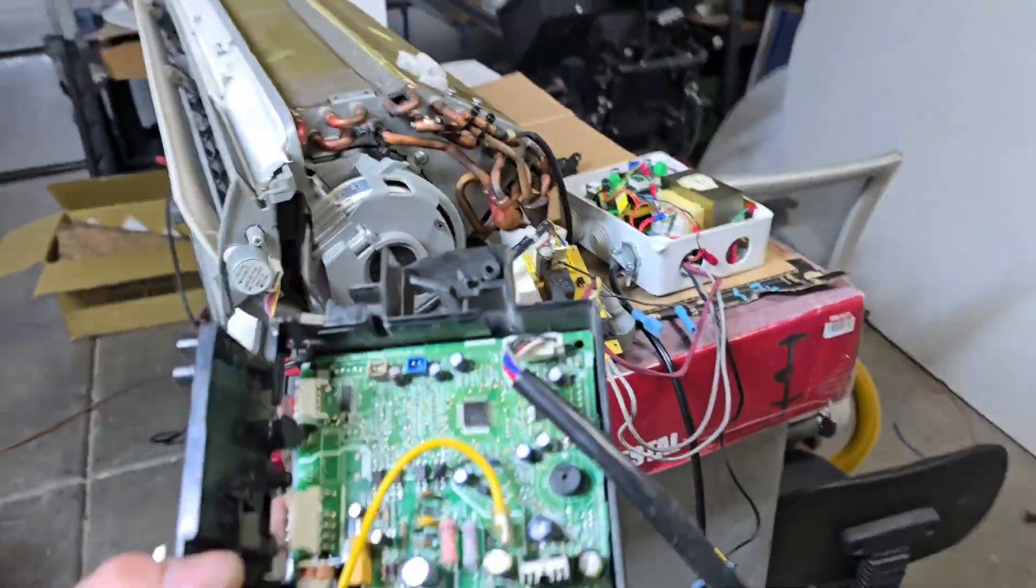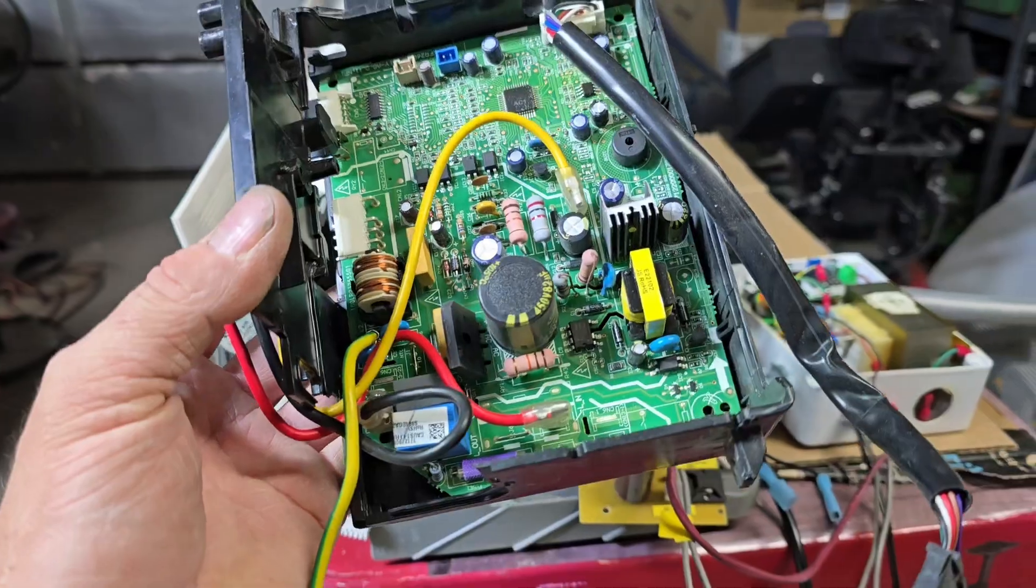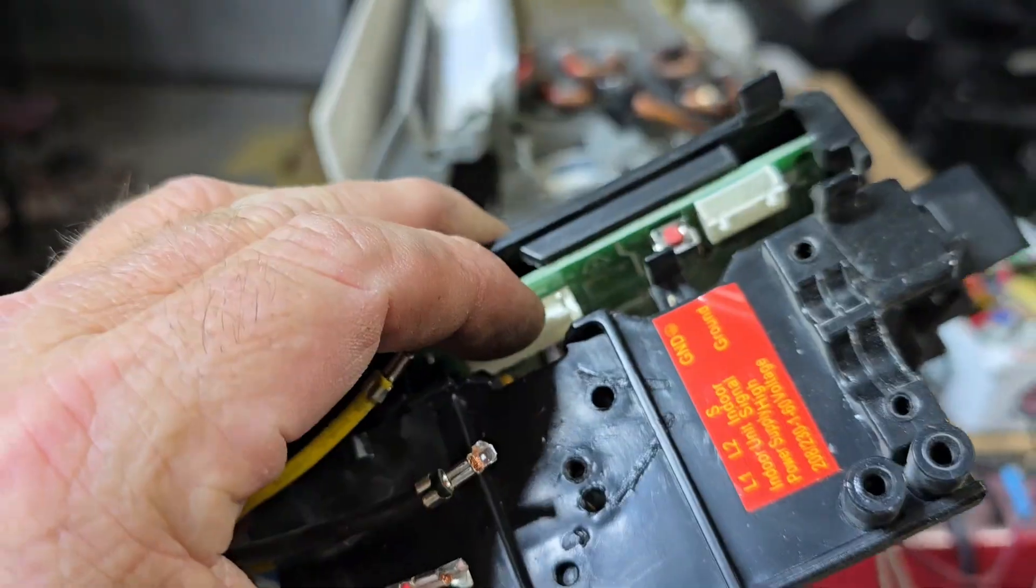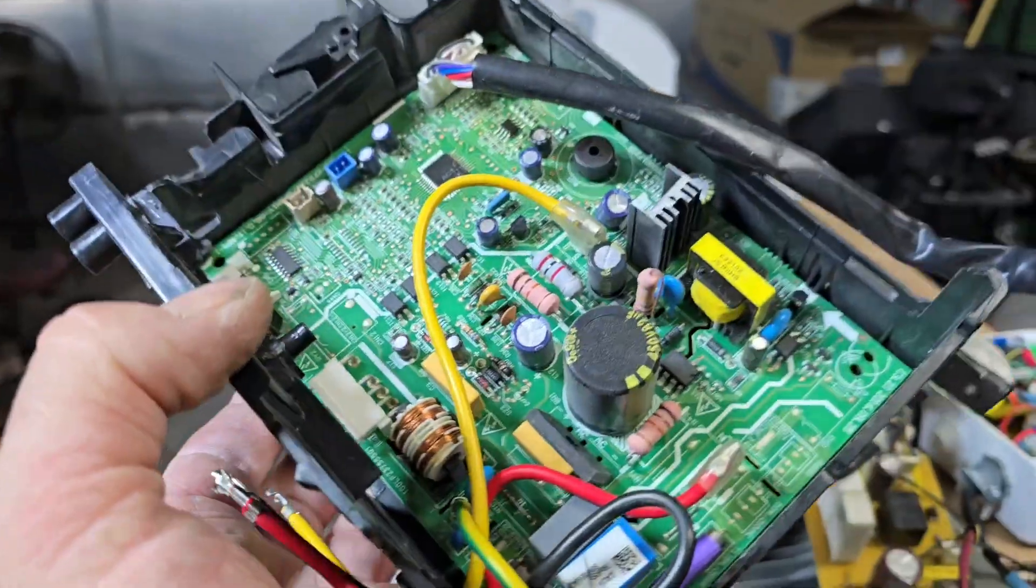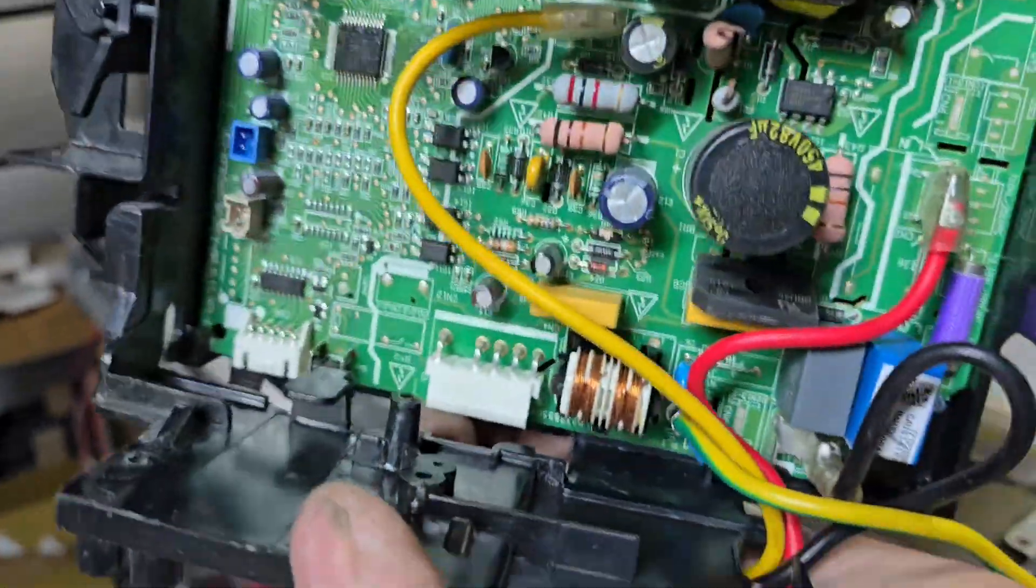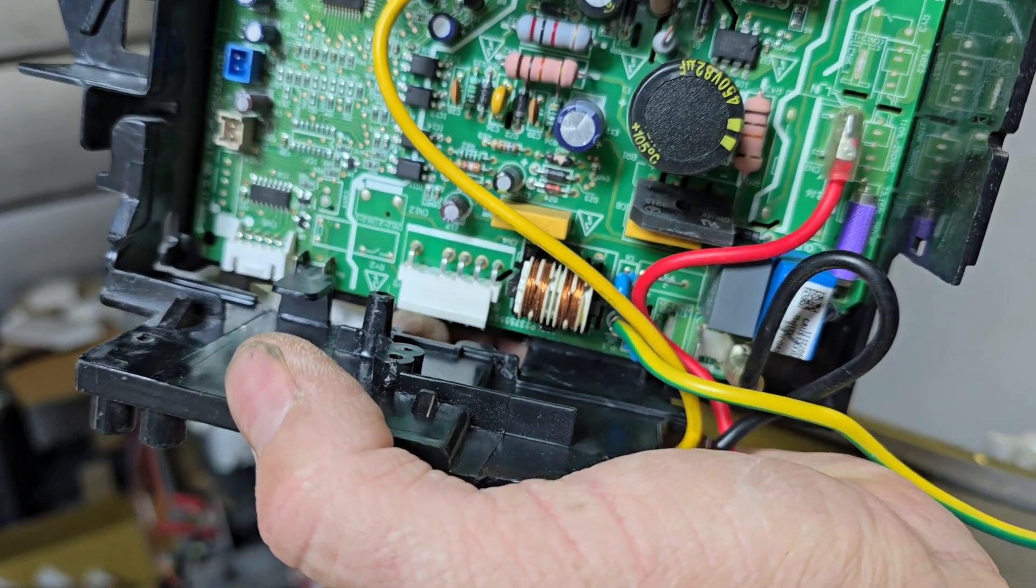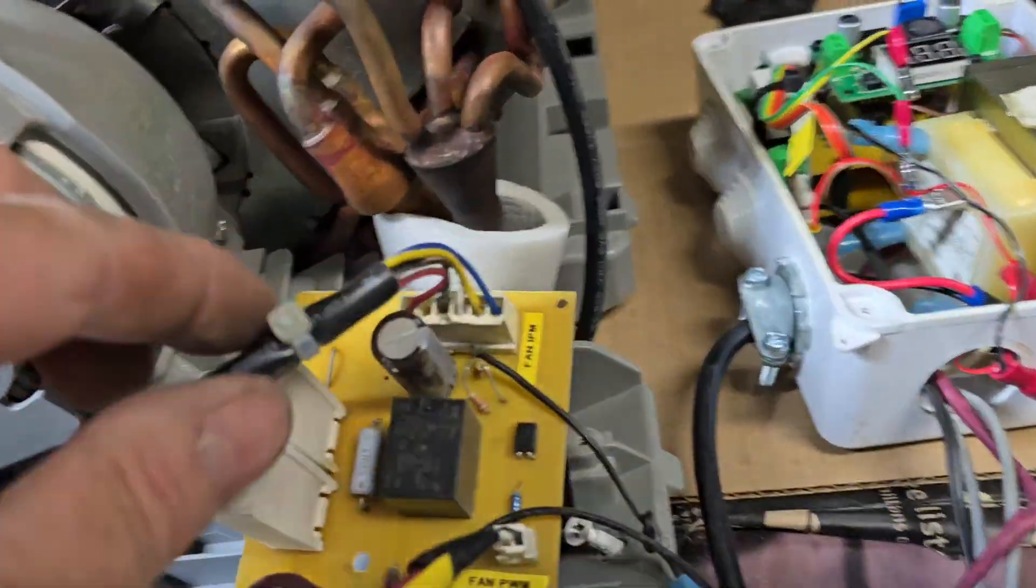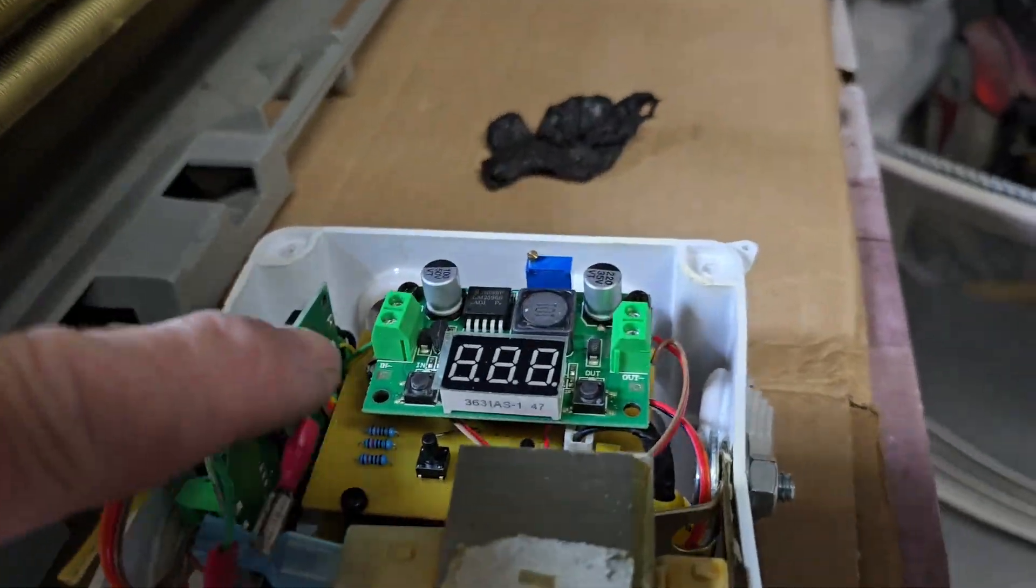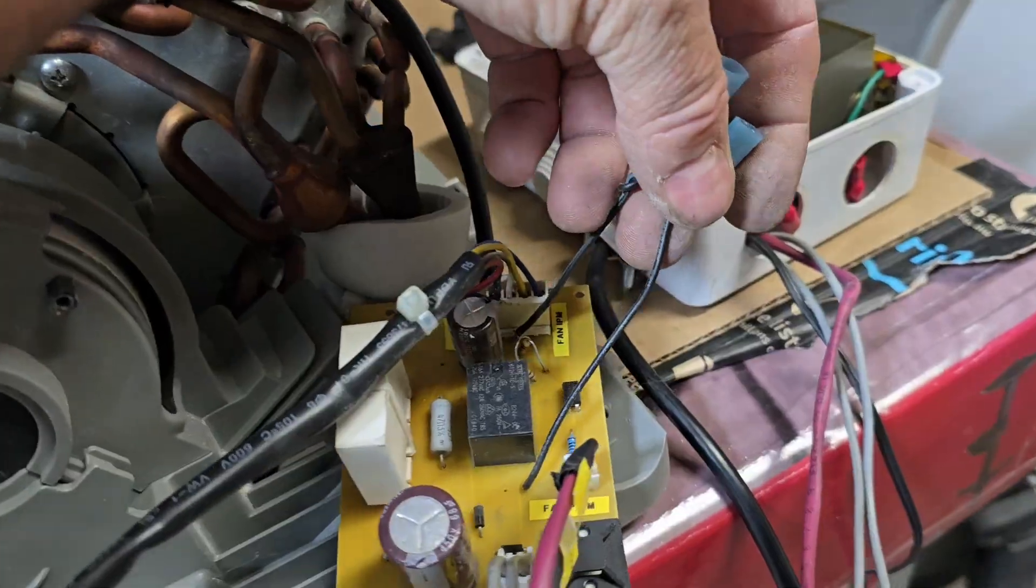Let me go get the board. Here's the board that comes out of there. This has the power supply for the motor, so you got your capacitor, full-wave rectifier, and your fan motor plugs in right here. You got DC power going to it at these two terminals, and then it's like 15 volts I think. One to six for the motor and then feedback. It's plus, minus which is common, which is pin three, goes, skips pin two, three is your 15, and then actually four, five will be the one to six, and the six pin will be feedback.